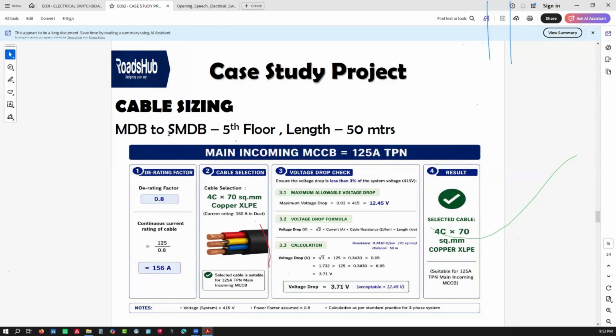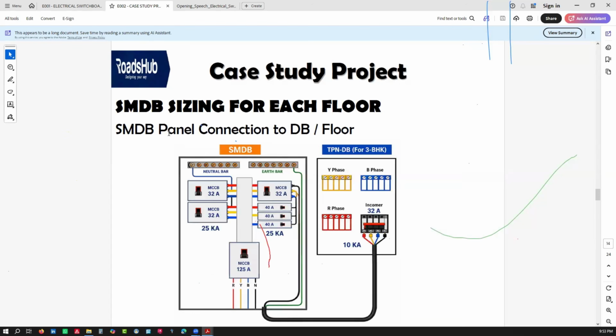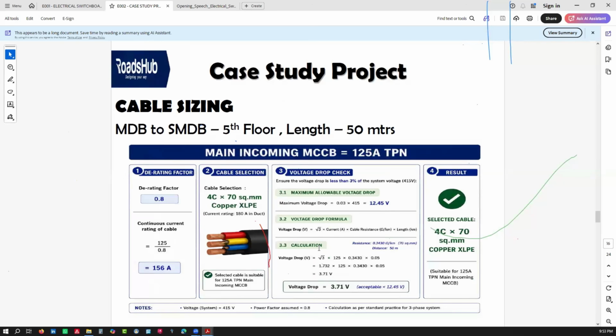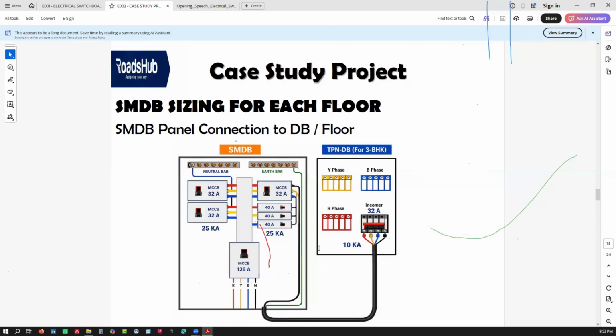So if you go to the next slide, I've now shifted to the cable sizing. Remember, you see this cable coming from the SMDBs going to the houses. You need to know how much cable size you need. That's when you go through the cable sizing method. The cable sizing method is simple. You just need to know how much current the system or the breaker that you're supplying has. So all the SMDBs actually have a 125, and we selected that here. You can see the main breaker, it's a 125.